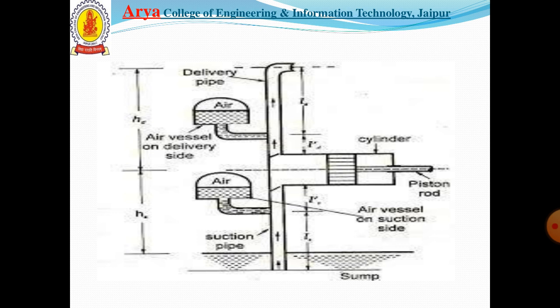When the piston forces the liquid into the delivery pipe with a velocity greater than the mean velocity vd, the additional liquid moves into the air vessel. When the velocity is less than vd, the additional liquid flows out of the air vessel and makes up the deficiency.